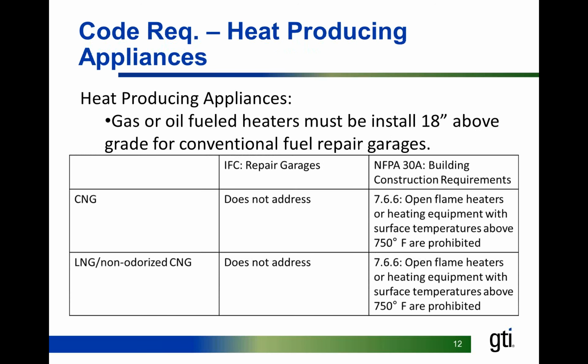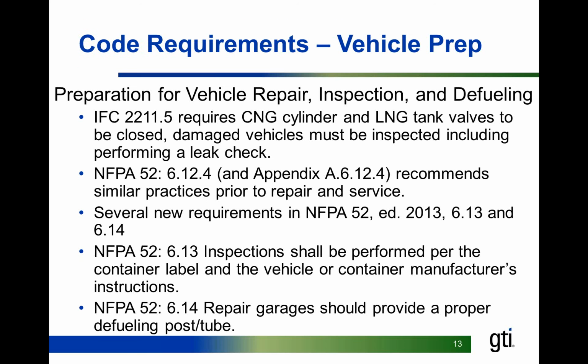The other major concern is heat-producing appliances, and that's often open flame heaters that are in many garages. If you're using natural gas, open flame heaters or anything with a surface temperature above 750 degrees F are prohibited, and that's in the major, or depending on the interpretation, that can be in major and minor areas. That's just a key in order to keep flammable mixtures of lighter than air fuels from rising up and touching an open flame heater.